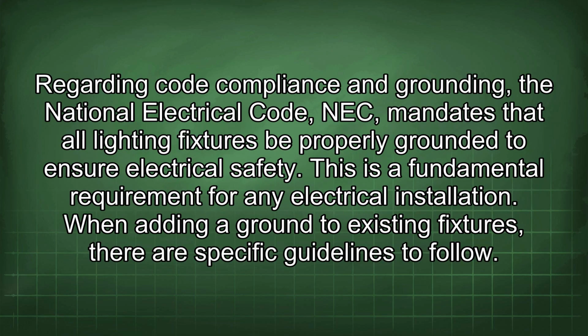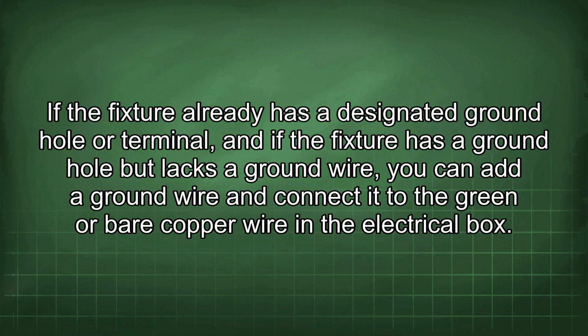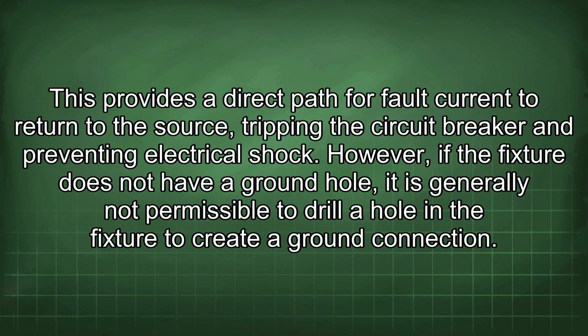Regarding code compliance and grounding, the National Electrical Code (NEC) mandates that all lighting fixtures be properly grounded to ensure electrical safety. This is a fundamental requirement for any electrical installation. When adding a ground to existing fixtures, there are specific guidelines to follow. If the fixture has a ground hole but lacks a ground wire, you can add a ground wire and connect it to the green or bare copper wire in the electrical box. This provides a direct path for fault current to return to the source, tripping the circuit breaker and preventing electrical shock.